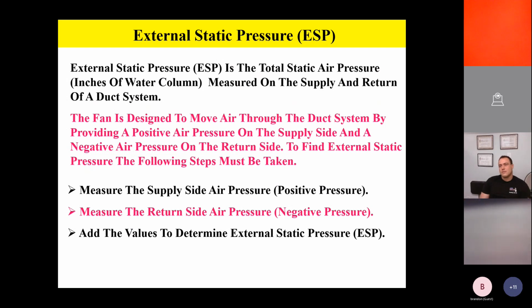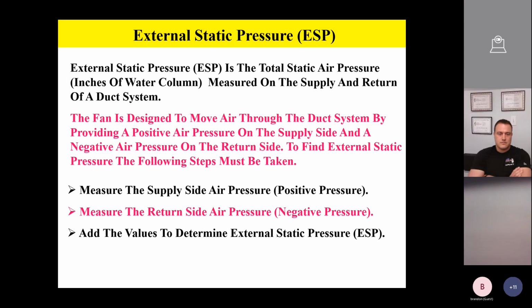And here's why. If I measure my supply side pressure first, and then my negative pressure or my return side pressure second, and you don't have to do it in that order, you could flip-flop the order, but if you take those air pressures separately and then add them up, I believe, in fact, as I know, you get a better rating. Because sometimes if you have a duct system that's providing some internal turbulence, and you try to take those 2 pressures together, in other words, they're being read together on the gauge, you can actually be in a situation where you're trying to average 2 turbulent air sources based on the duct system.